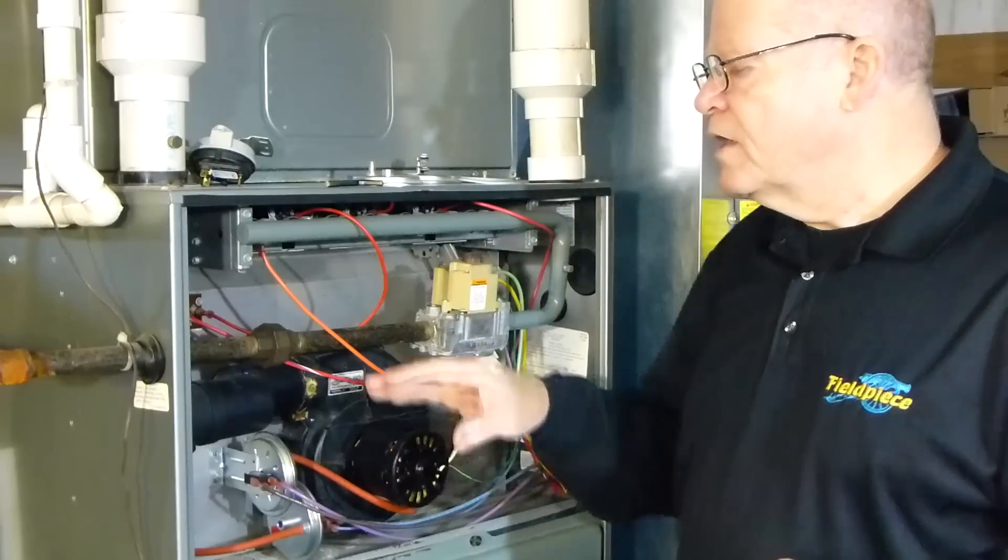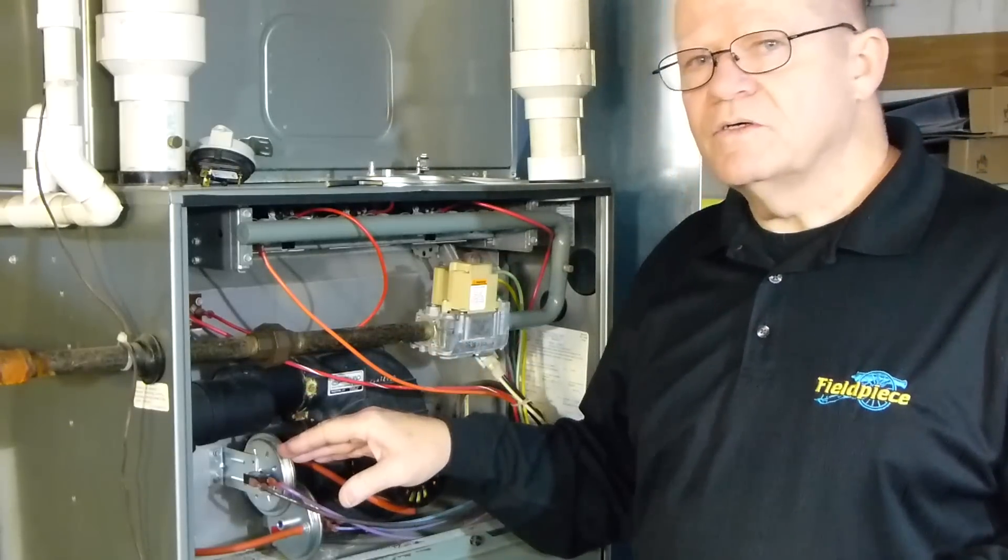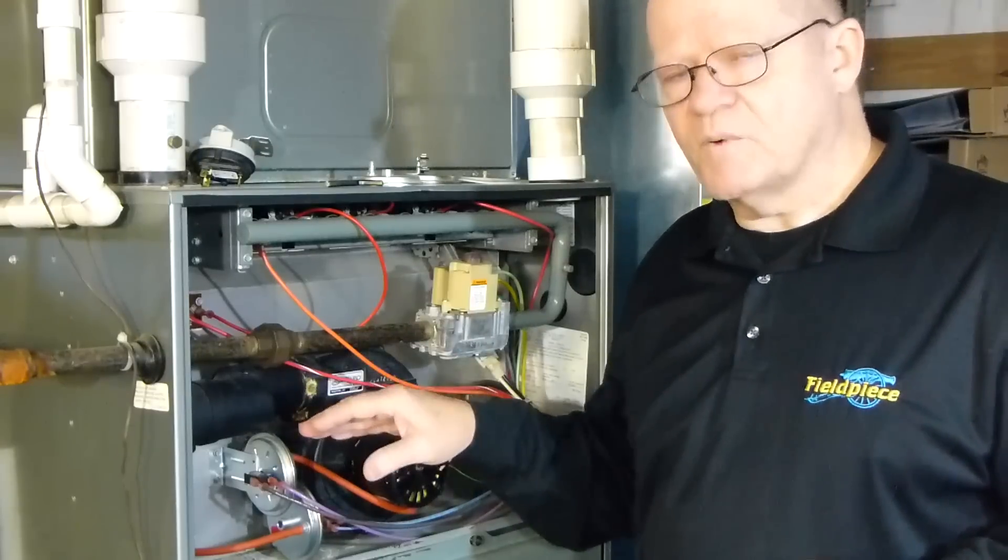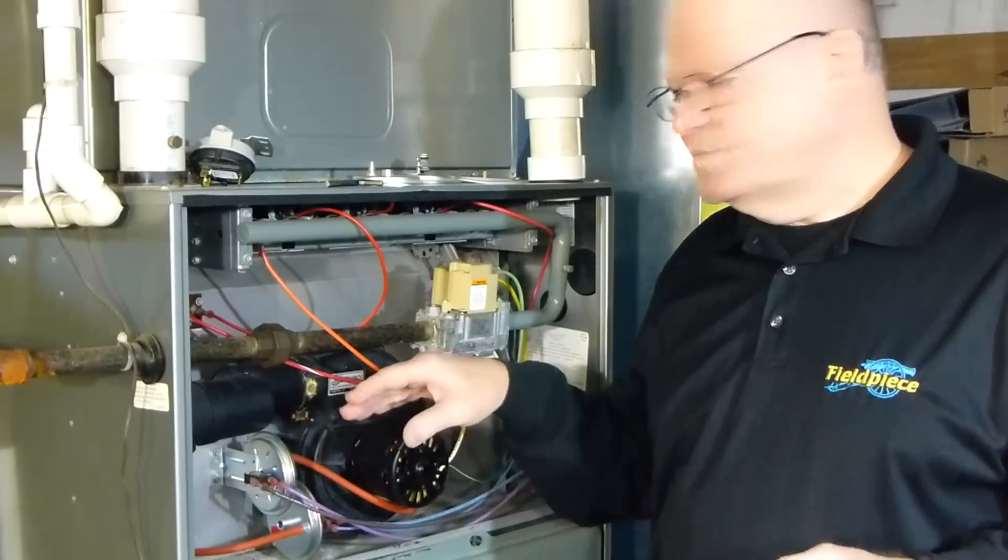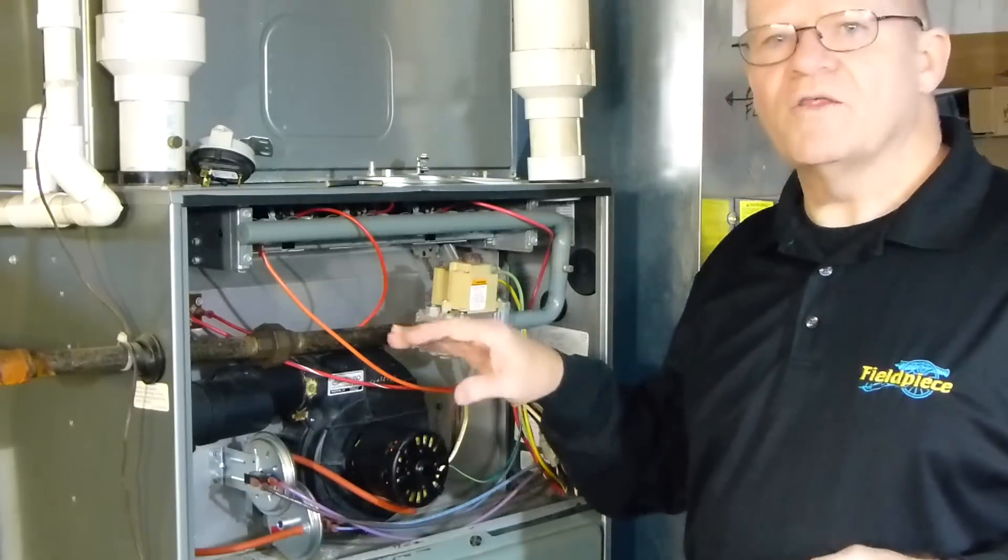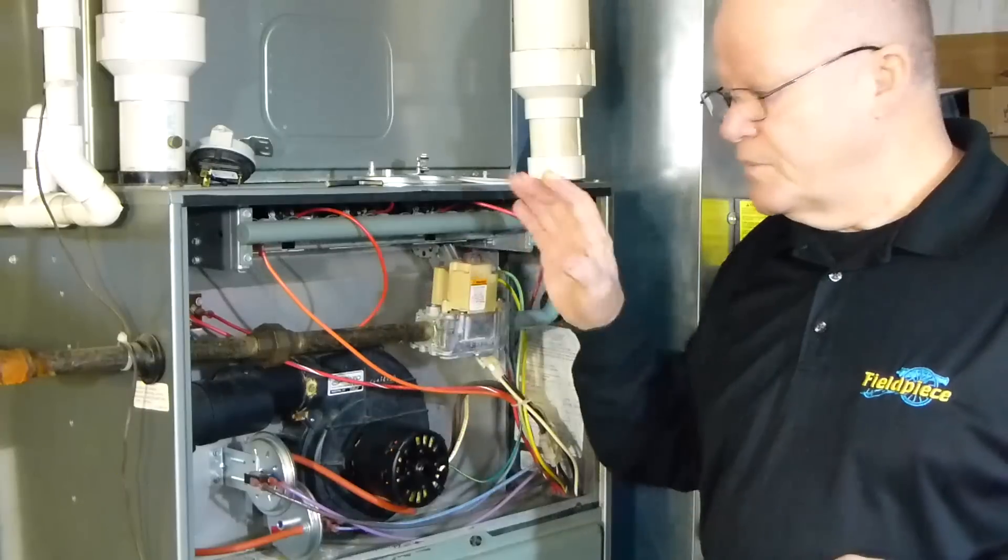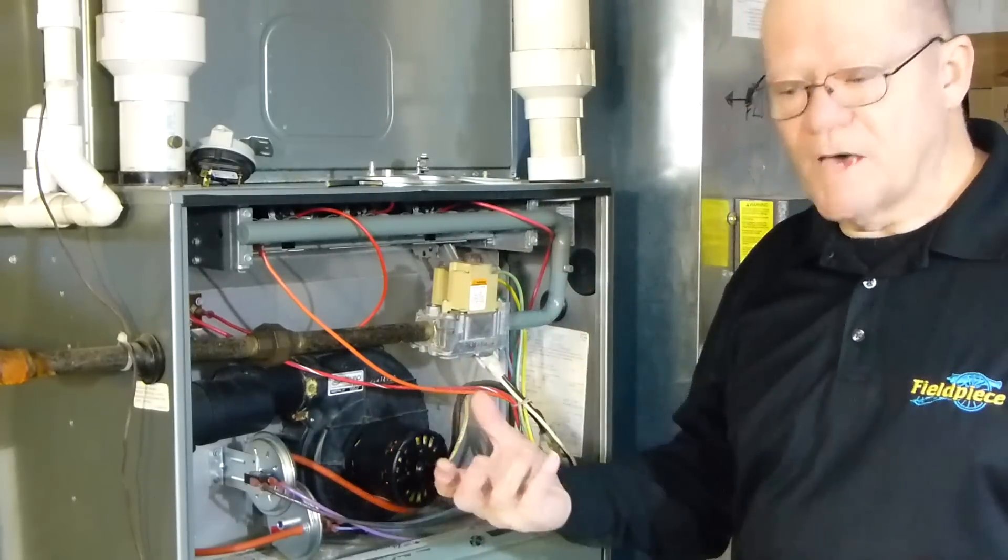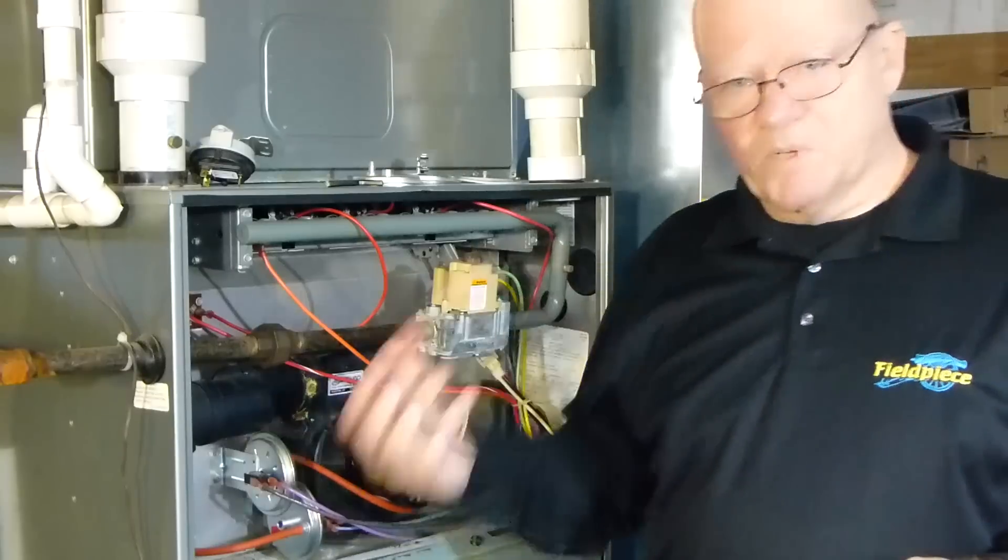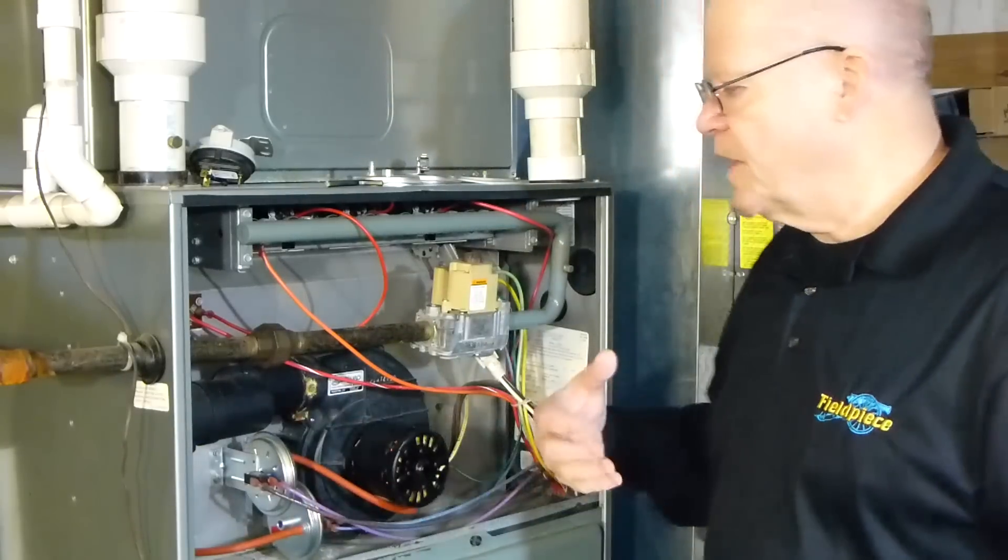Now, all of that being said, don't try to calibrate or recalibrate a pressure switch that came with the furnace. There is a reason it failed, so I would not do that. What I would do is replace the switch.